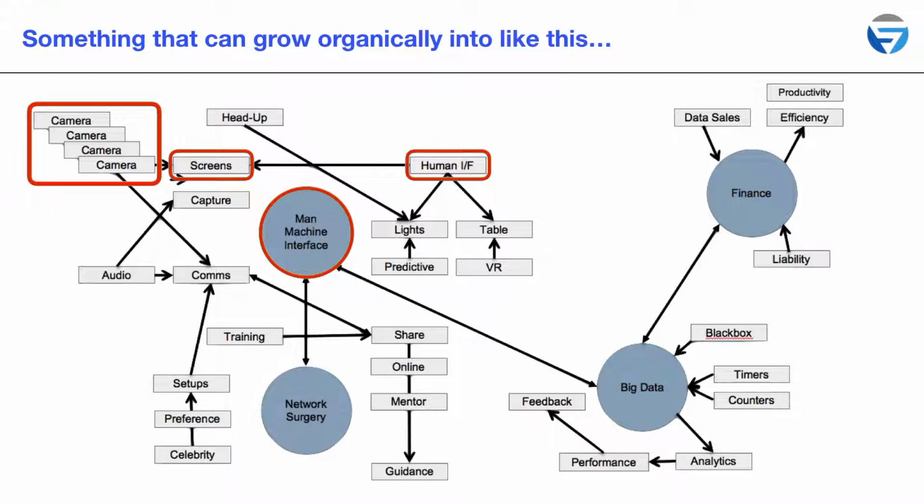We have seen enhancements to that. We can add a capture, so we can actually take some photographs of the procedure. Other companies have done device control, so they control the operating room lights, and they can control the positioning of the table, all from the same human interface. And these closed systems tend to be based on proprietary controls. Every manufacturer, every company has their own bus for communication. So interoperability is not possible.